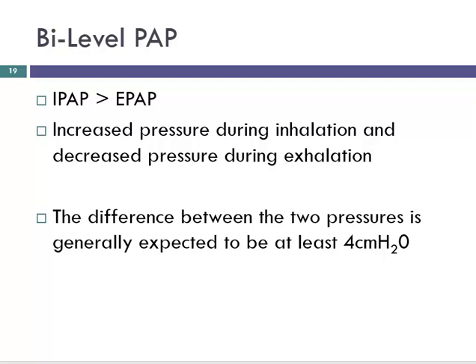The difference between inspiratory and expiratory pressure has to be at least 4 centimeters of water pressure. So if you have an inspiratory pressure of 9, the expiratory has to be 5 or below. You can't have it at 9 and 6. They have to be at least a 4 pressure difference.